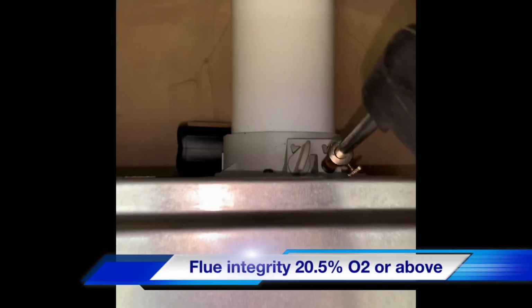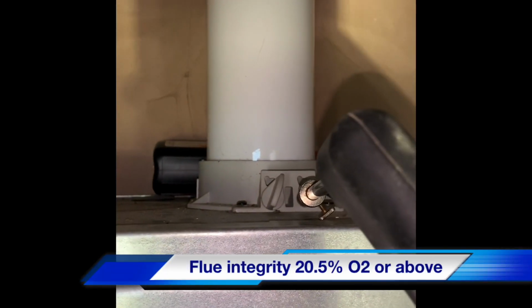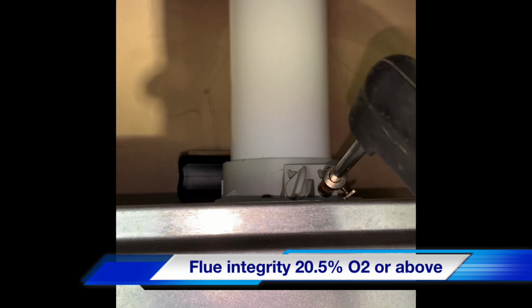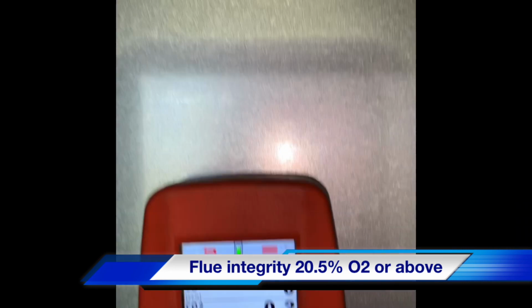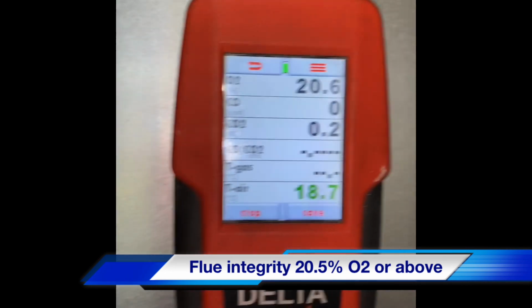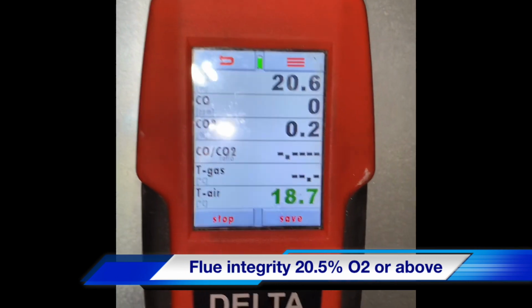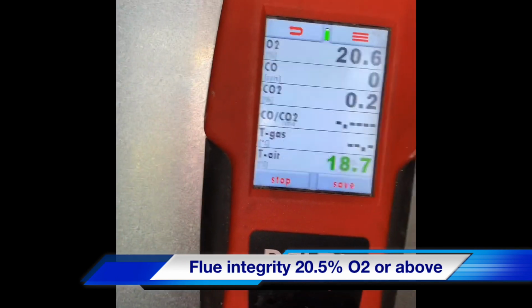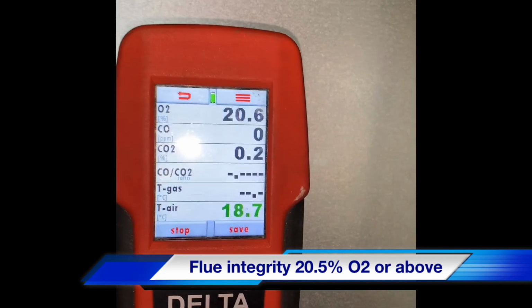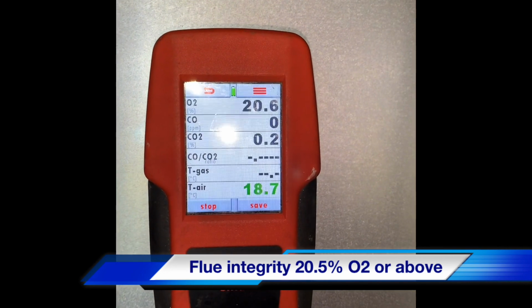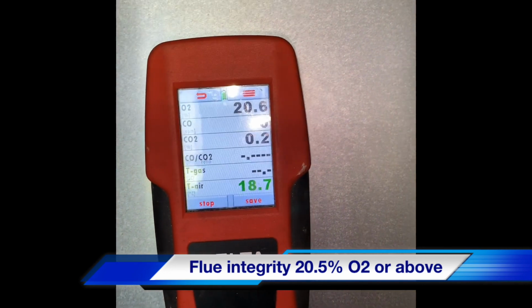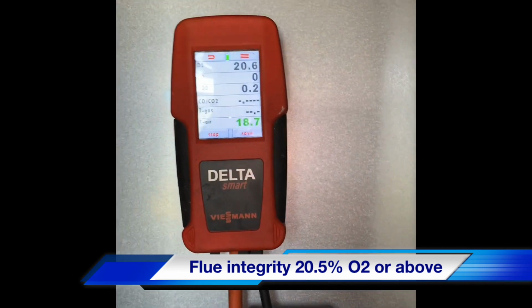Now carrying out a flue integrity test. So we've got the flue sample point in the air side of the flue, and we're checking the oxygen level, O2 level coming in. So we're looking for above 20.5, which is that reading there. So that's indicating to me that this boiler is bringing in fresh air for combustion, which is what it is.